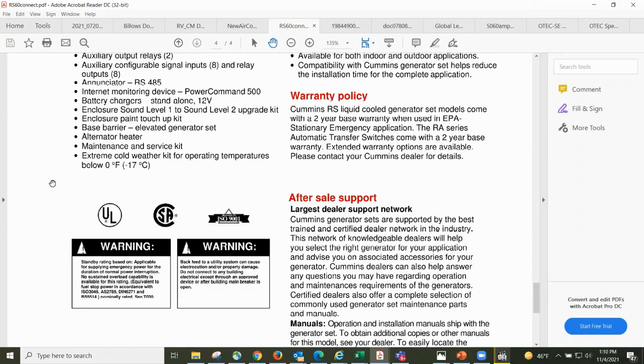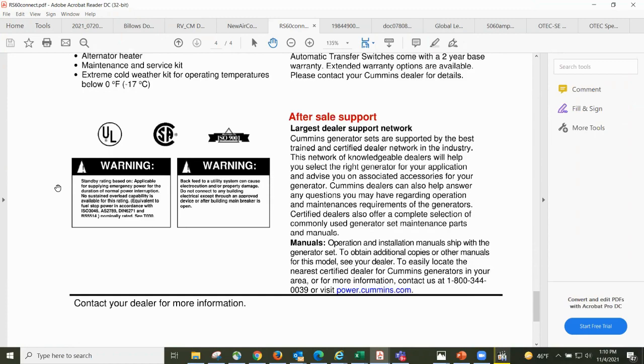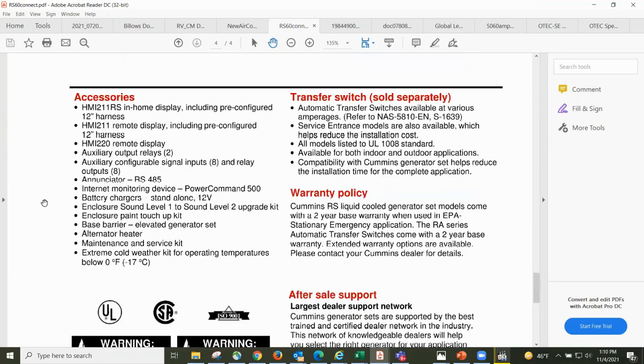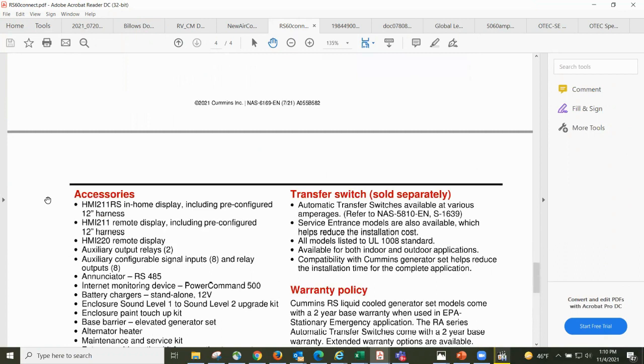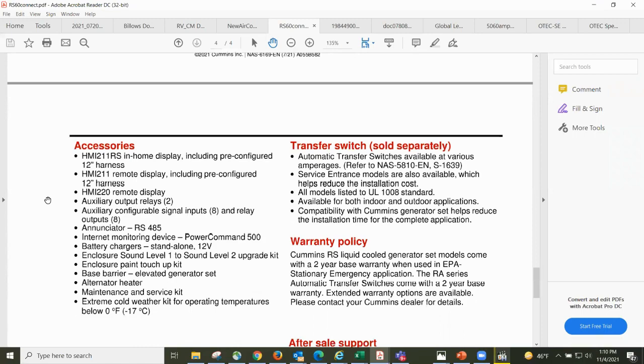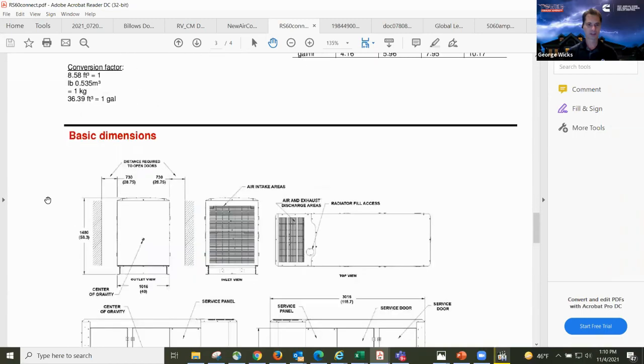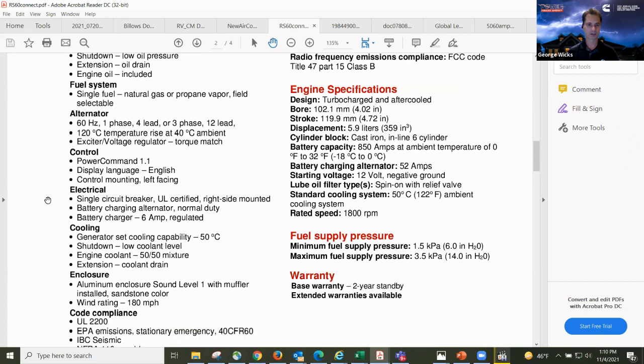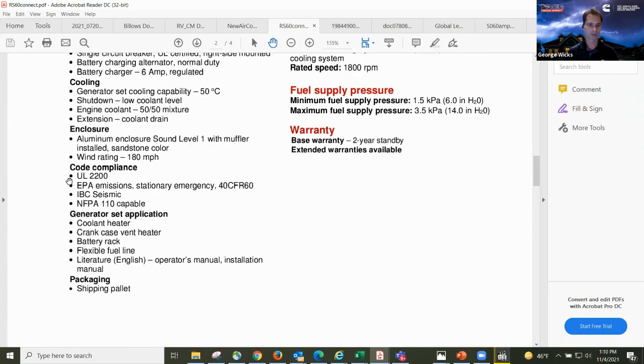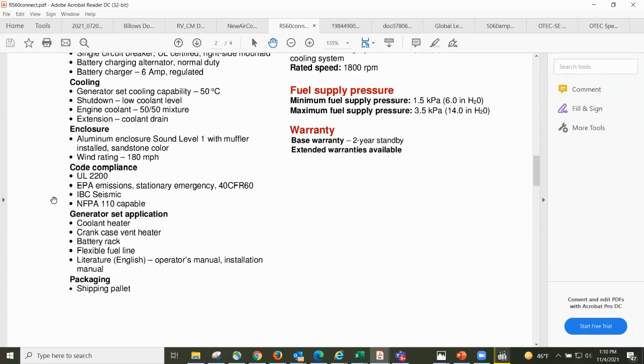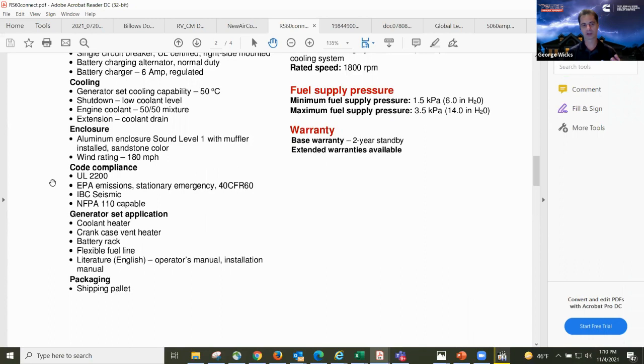Yes, the transfer switch, I remember them. There, yeah, on the right—scroll up a bit more please. Yeah, right there it says UL listed, that's the transfer switch, UL 1008. But now let's look at the genset. Yeah, this is a standby generator, code compliance, UL 2200. Yeah, so Kohlers and Generacs, we all have to comply with that if we're going to sell in the United States. Right, and same with EPA standards, we all have to meet that.